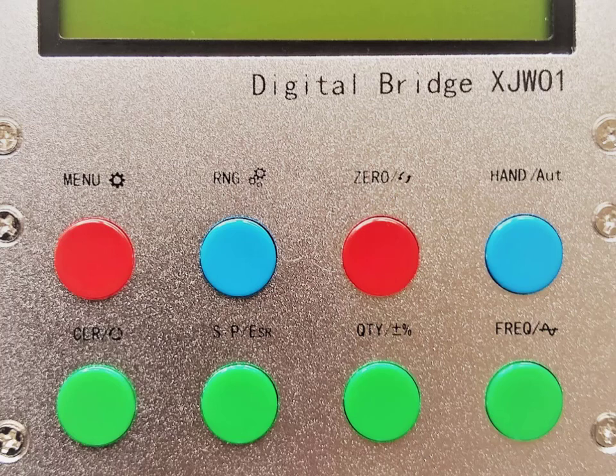to take another reading. Now you should do this each time you connect different probes, or change the probe connections around, or switch the unit on, and theoretically you should allow 10 to 15 minutes of warm-up time before you actually do this. The next button is marked Hand Auto, and this means manual, so hand means manual. So instead of automatic mode, when you press this button it goes into manual mode, and in manual mode you can change the internal ranges.